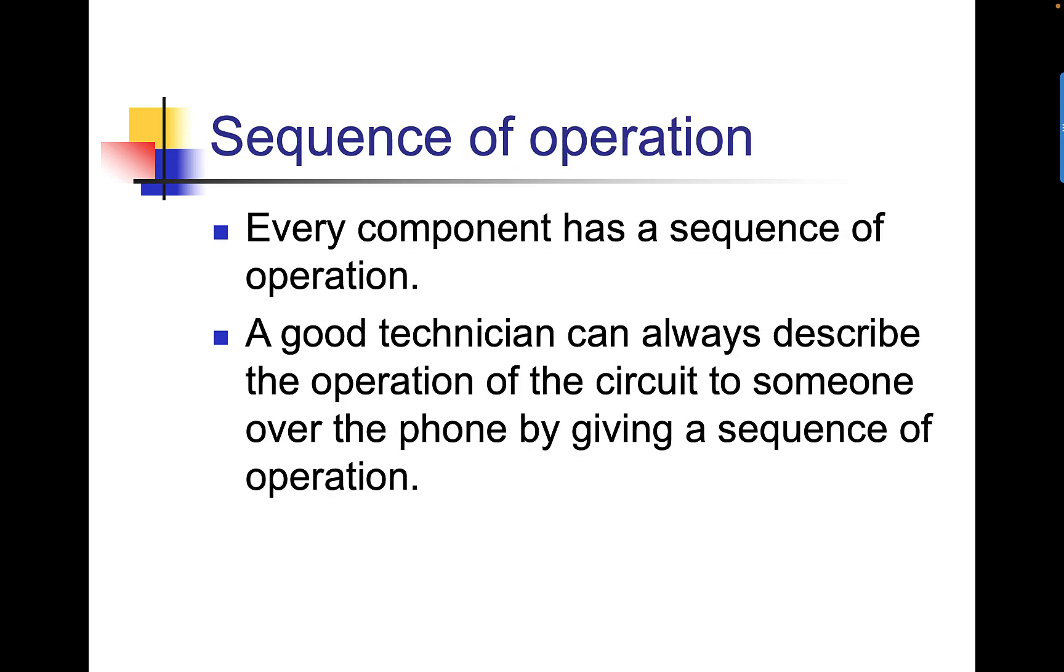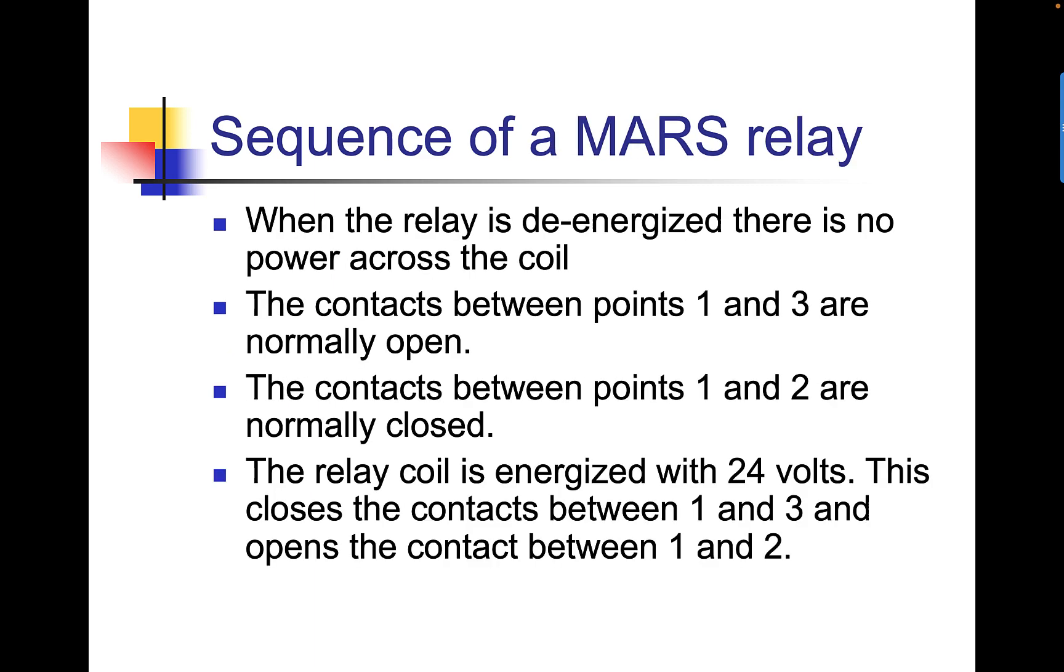Every component has a sequence of operation. A good service technician can always describe the operation of a circuit to somebody over the phone by giving a sequence of operation. When the relay is de-energized, there's no power across the coil. The contacts between points 1 and 3 are normally open. The contacts between points 1 and 2 are normally closed. The relay coil is energized with 24 volts. This closes the contacts between 1 and 3, and opens the contacts between 1 and 2.